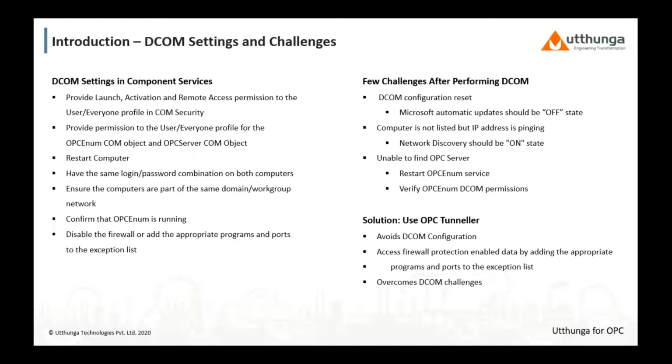The second issue might be that the computer is not listed, but the IP address is still pinging. Which means there is an option called network discovery, and you should have it in the on state. Then, unable to find the OPC server. In this case, you may need to restart the OPC Enum service.